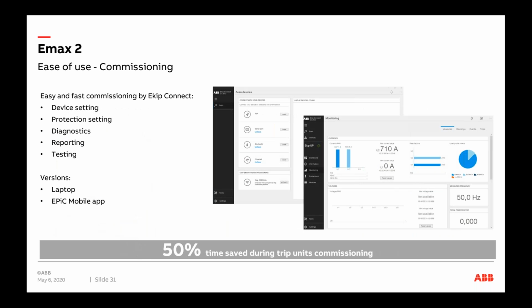Then in terms of commissioning, our Ekip Connect software is quite straightforward to use. We have that in place to not only be able to connect the Emax 2 to ABB Ability EDCS, but also program the breaker. So protection settings, being able to select logics with digital inputs and outputs. So if you're looking at certain digital inputs and outputs to be functioning and pulling out alarms to go onto a PLC or being able to give us some information, all that's possible, especially with the hardwired digital inputs, outputs.